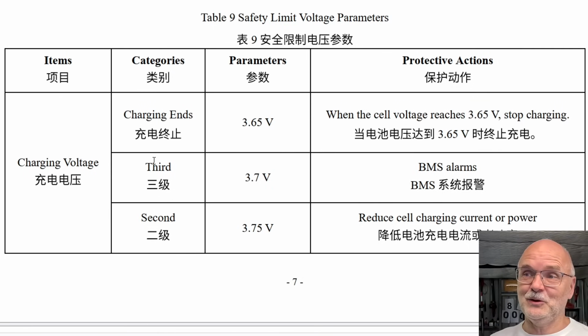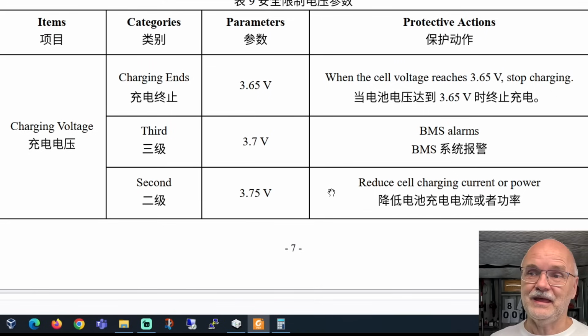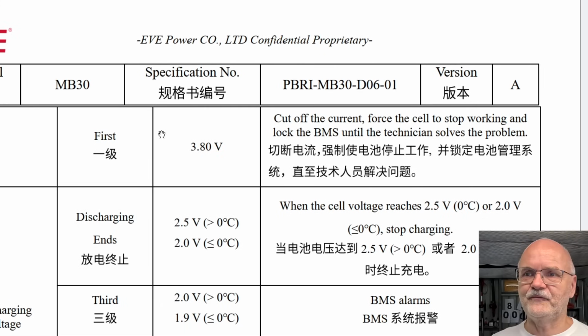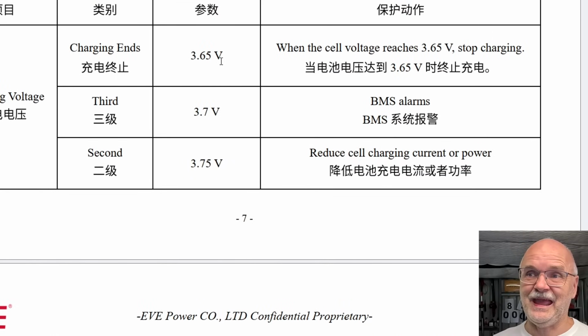And here it gives you actually an example of how to program your BMS. So it says at 3.65 volts, stop charging. At 3.7 volts, there's a BMS alarm coming. At 3.75 volts, reduce cell charging current or power. It goes even further. There's a first level of alarm at 3.8 volt, cut off the current, force the cell to stop working and lock the BMS until the technician solves the problem. So obviously something is wrong, because it clearly says here, stop charging at 3.65 volts. Yeah, everything else is a buffer, but I would highly recommend to set your BMS to an over voltage protection of 3.65 volts. Never ever charge your battery higher than 3.65 volts.